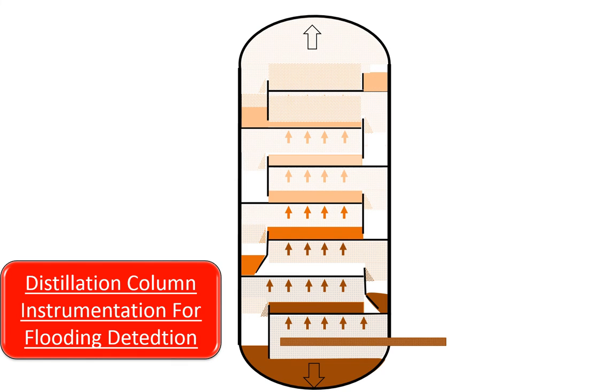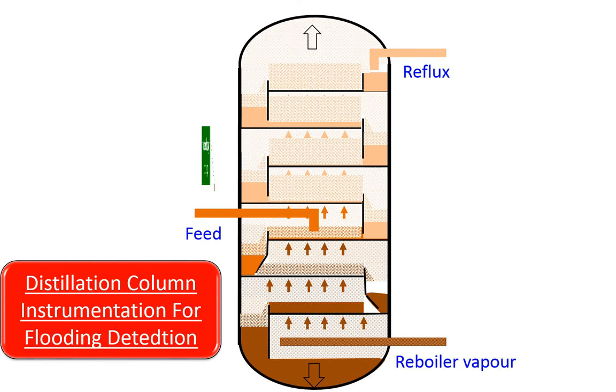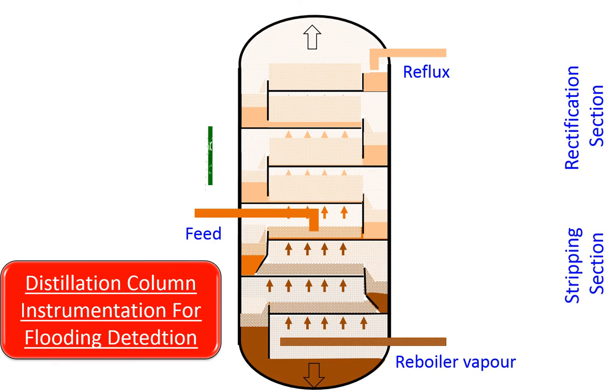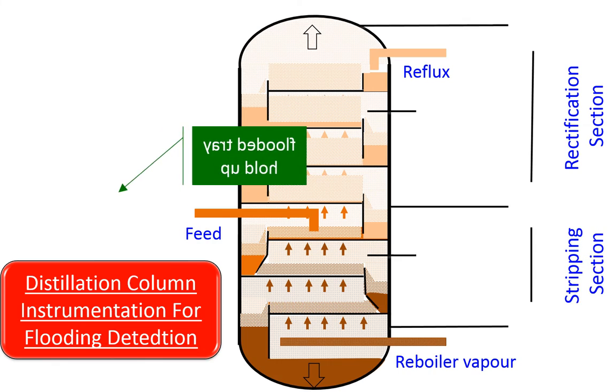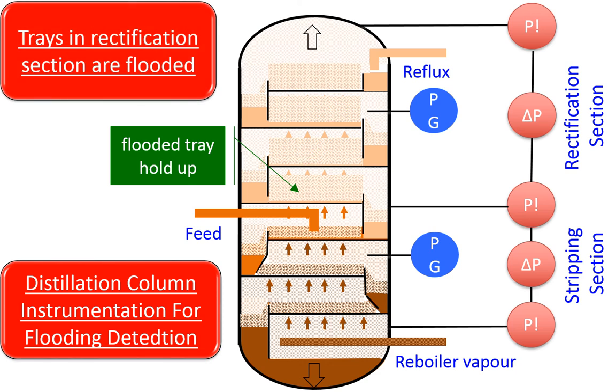This figure illustrates a distillation column where flooding is occurring above the feed tray. The liquid holdup in the trays above the feed has increased, causing the pressure drop to increase above the feed tray. This can be observed from the differential pressure transmitter in the rectification section.